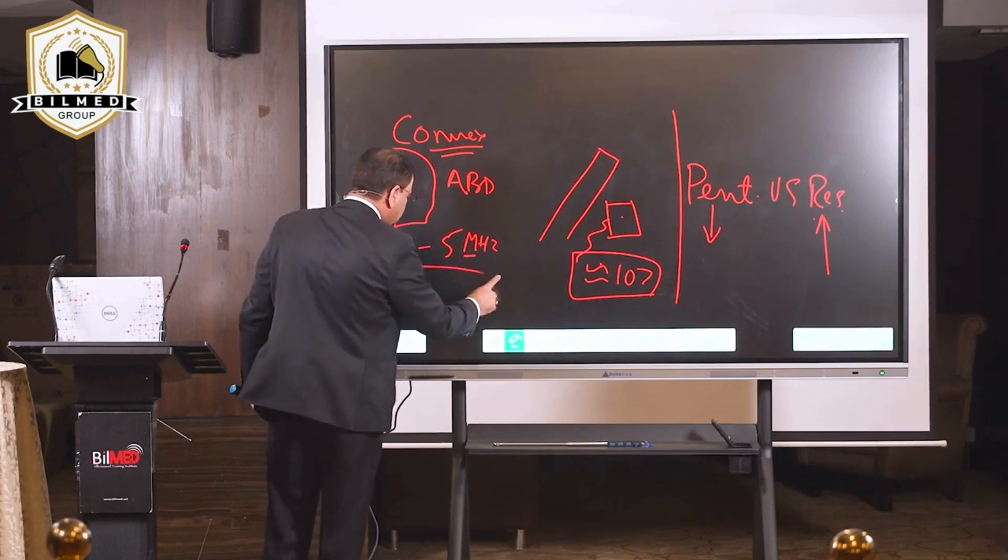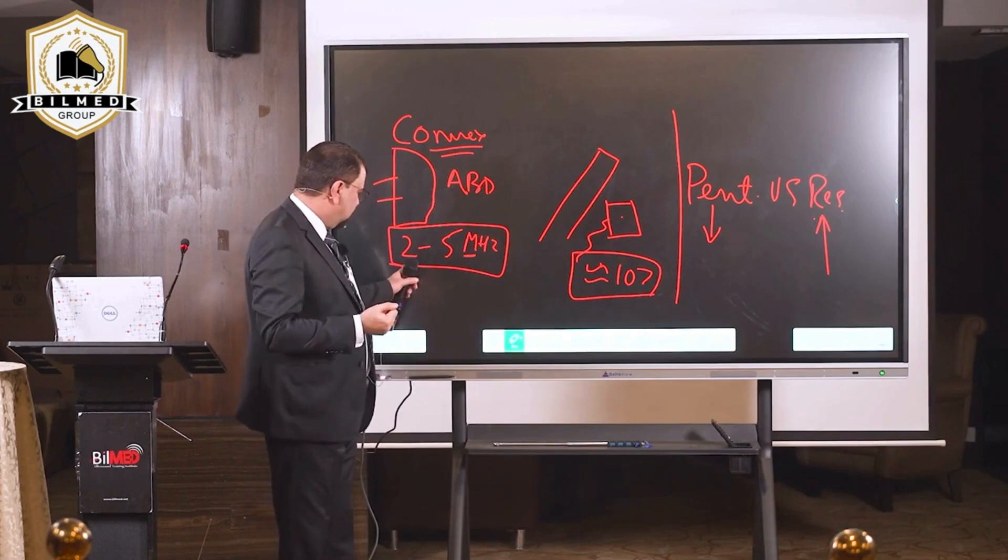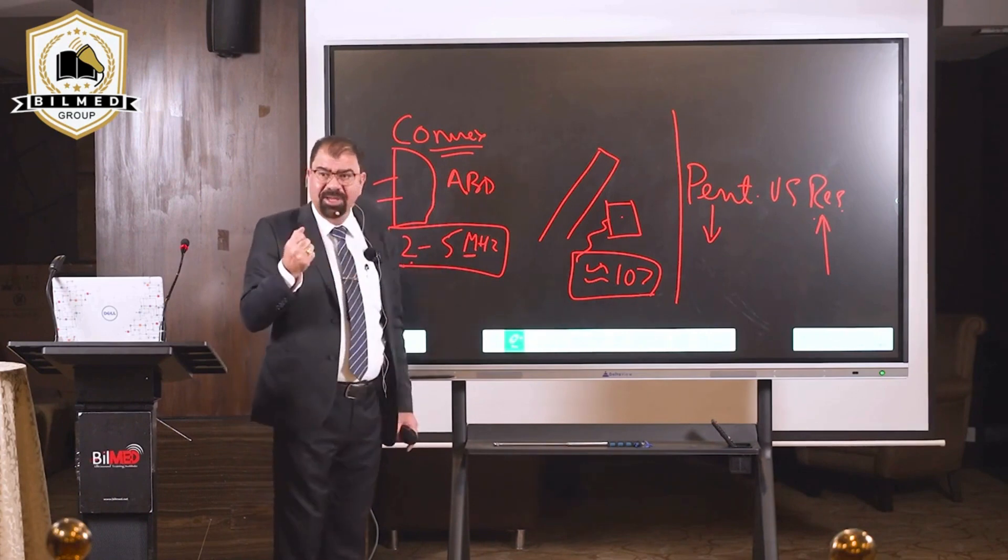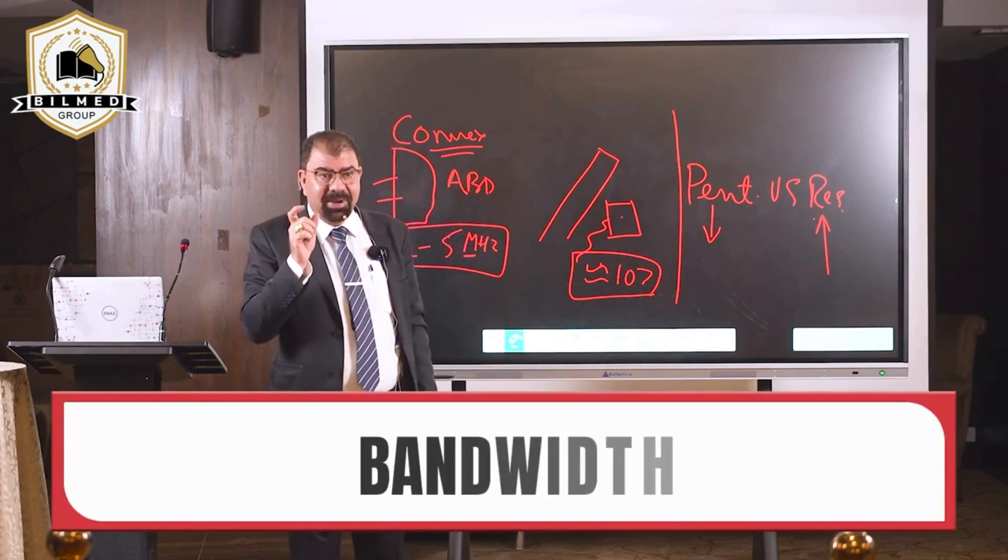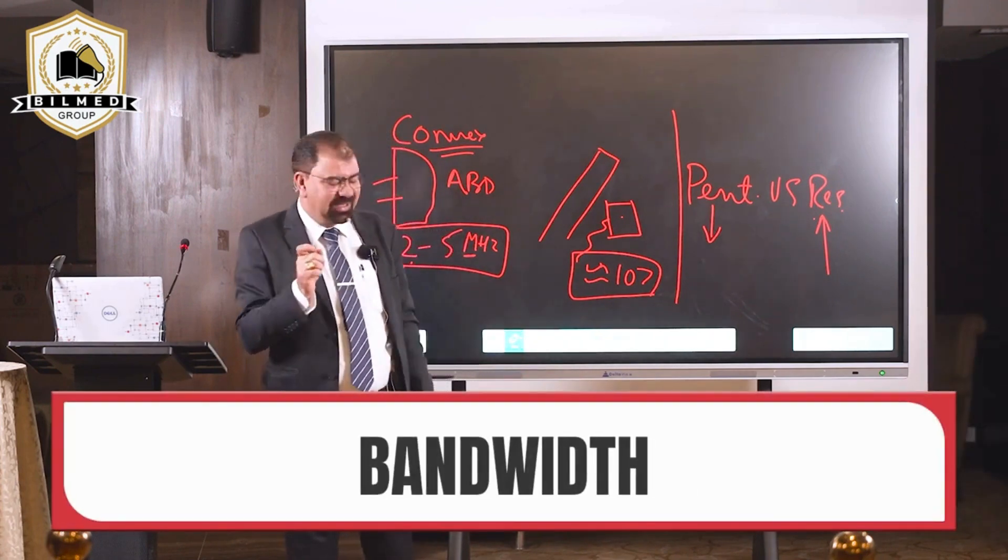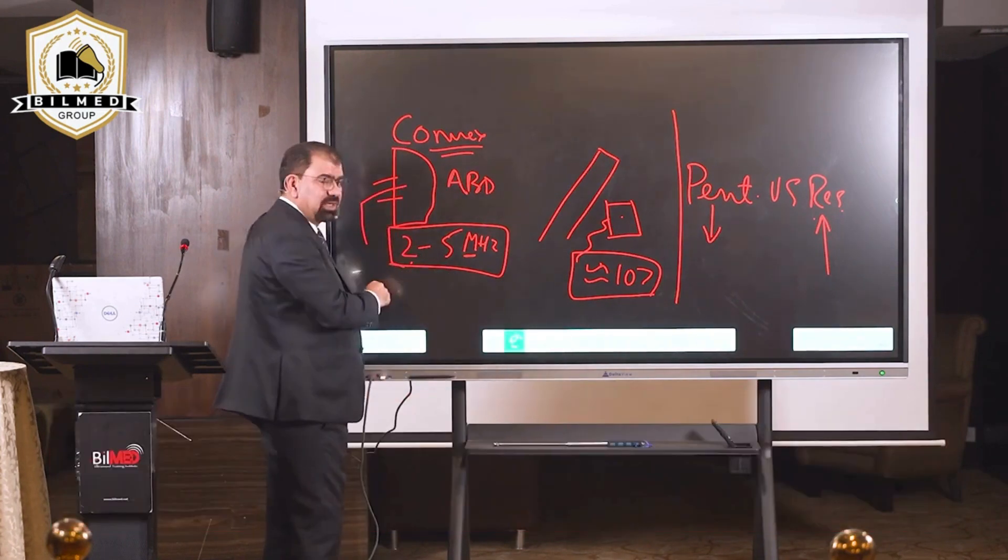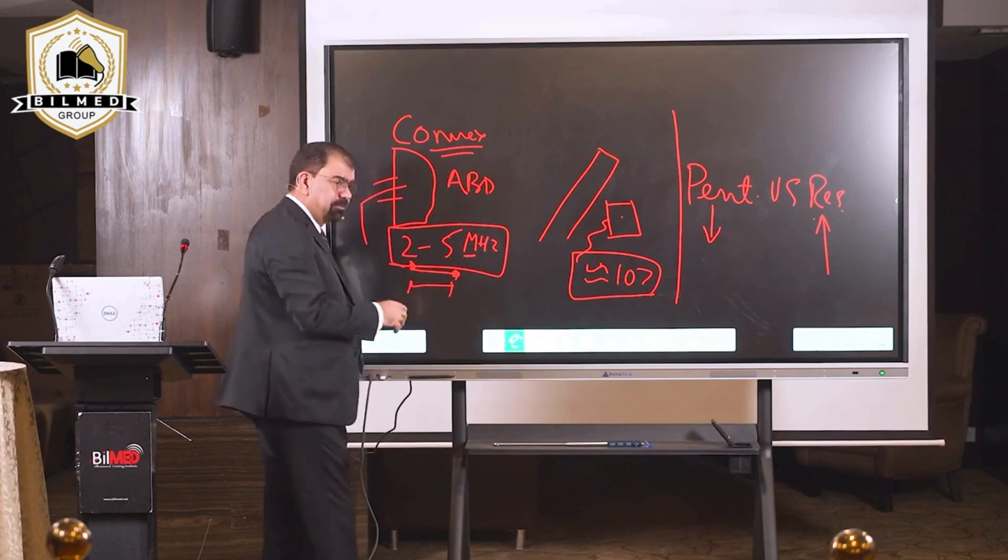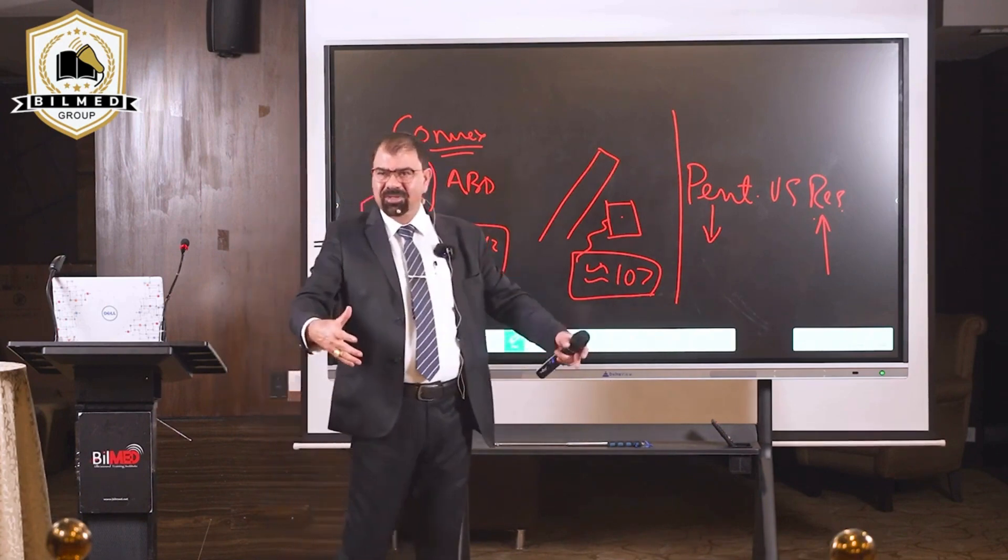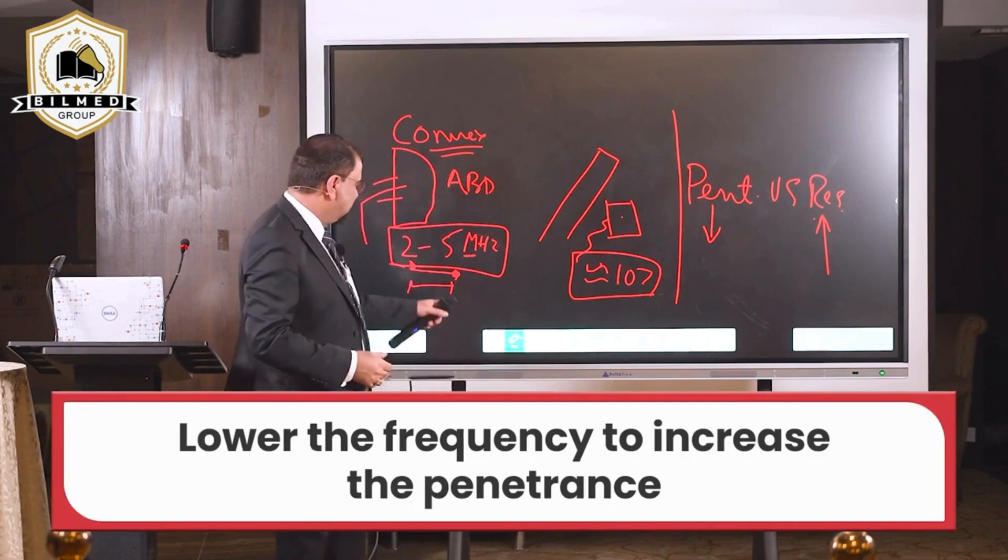What is this 2 to 5 MHz? This is the bandwidth. This probe's frequency can be changed between 2 and 5 MHz. If the patient is obese, you need more penetration, which means you have to decrease the frequency.